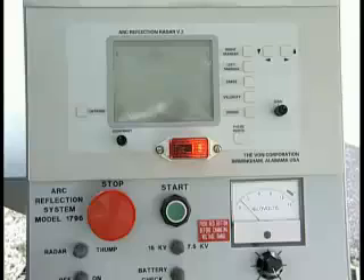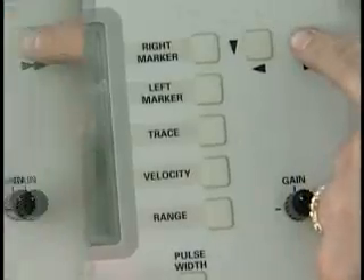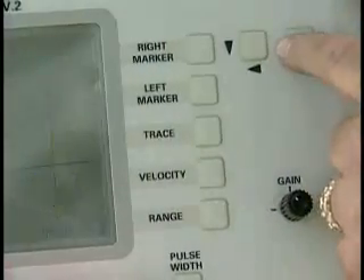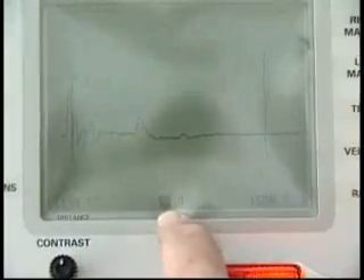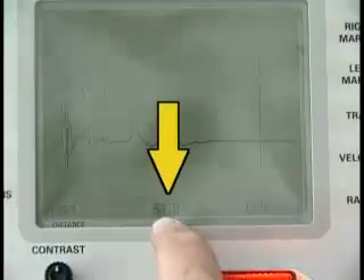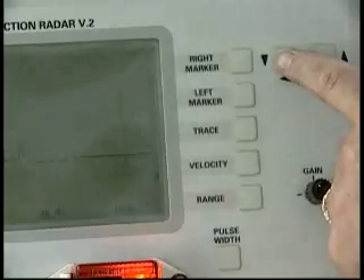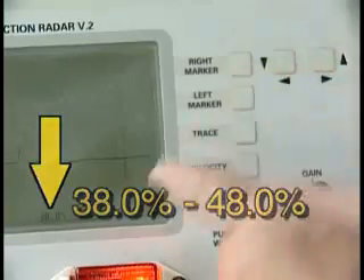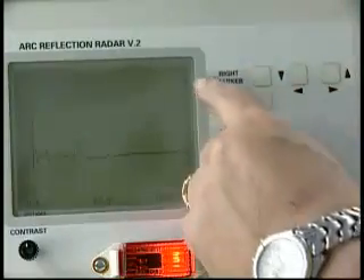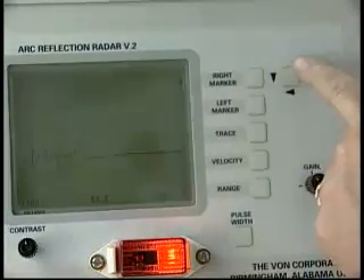Many features of the Von Arc Reflection System can be adjusted to fit your utility's needs. You can change the range of the radar trace from 500 feet to a maximum of 48,000 feet — some models have a maximum range of 24,000 feet. The velocity of propagation is based on a percentage of the speed of light and is set at the factory at 53.0% for extruded cable. If you're testing paper and lead cable, you can adjust the velocity from 38.0 to 48.0%. You can also manipulate the left and right markers — simply push the key next to the one you want and then use the arrow keys to move it in the direction you desire.